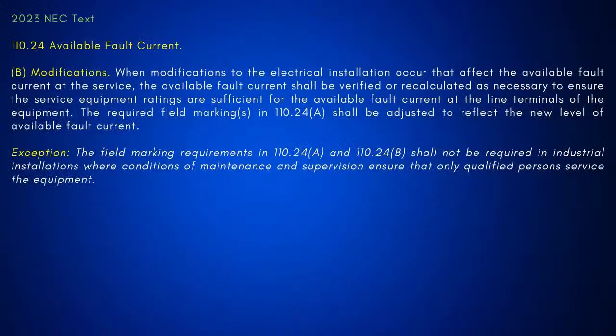I'm not done. Now let's look at one more portion. In 110.24(B), it talks about modifications. You're going to pay attention because I'm going to get to the next section, and you're going to understand why. It says when modifications to the electrical installation occur that affect the available fault current at the service, the available fault current shall be verified or recalculated as necessary to ensure the equipment ratings are sufficient for the available fault current at the line terminals of the equipment. So in other words, if I have to adjust those, I have to reflect the new level of that available fault current.